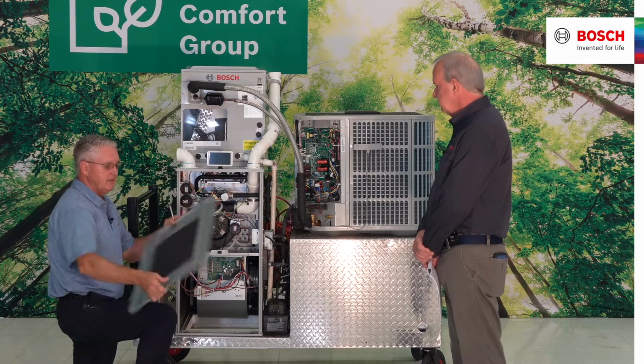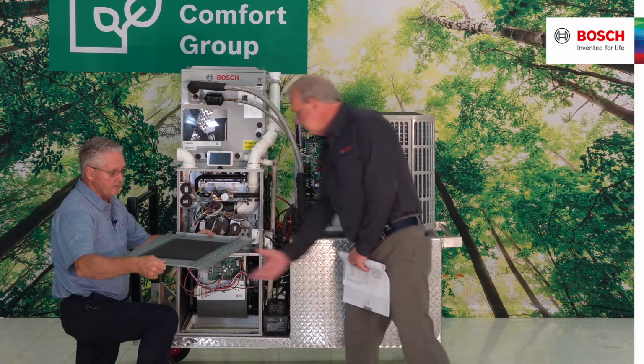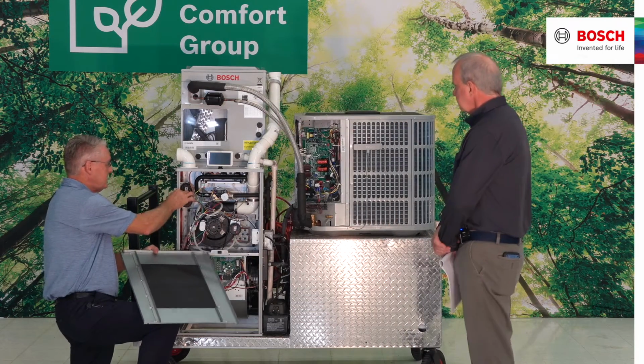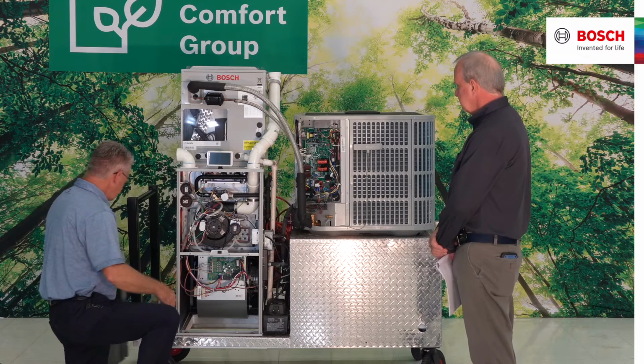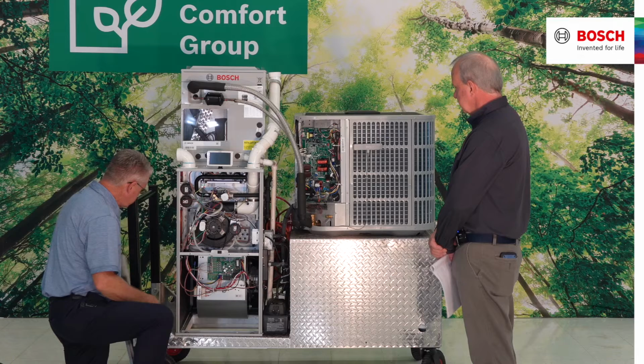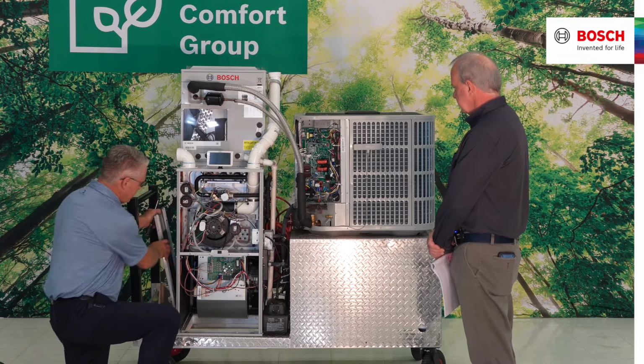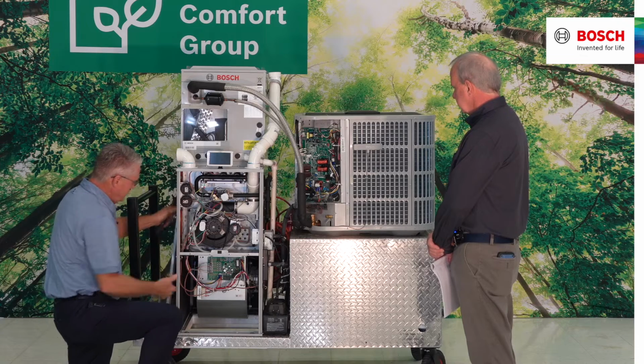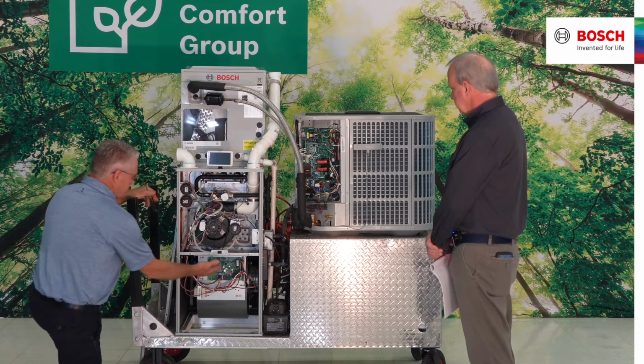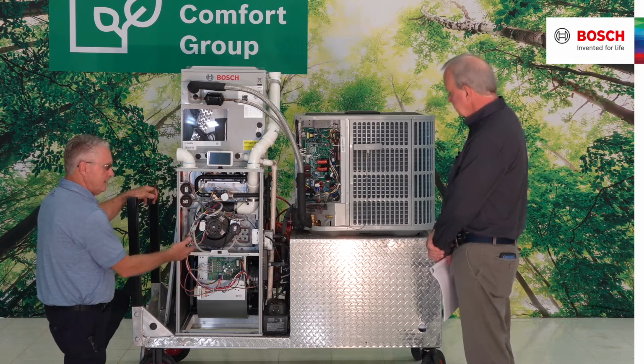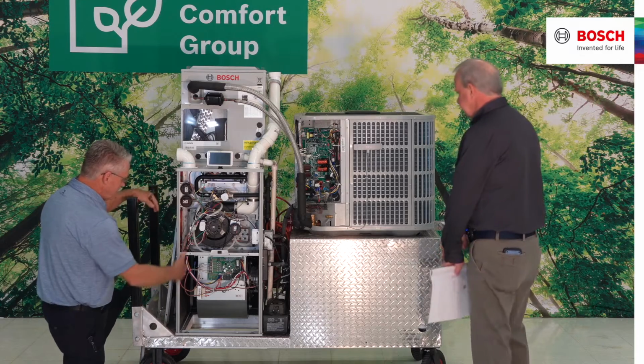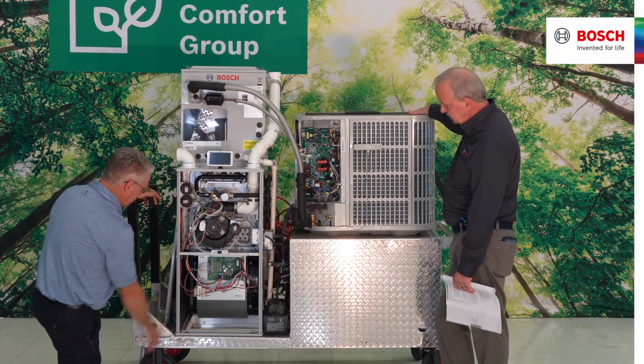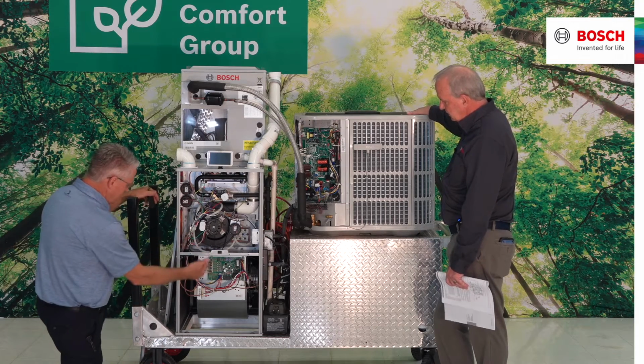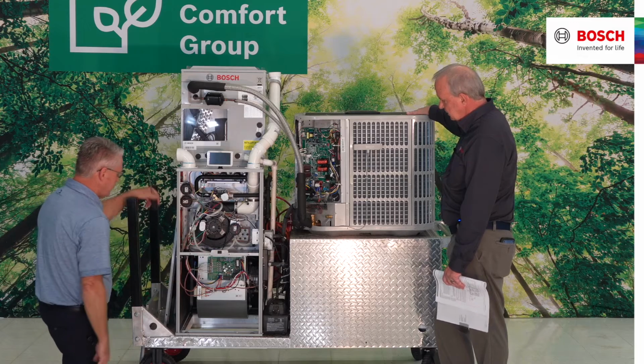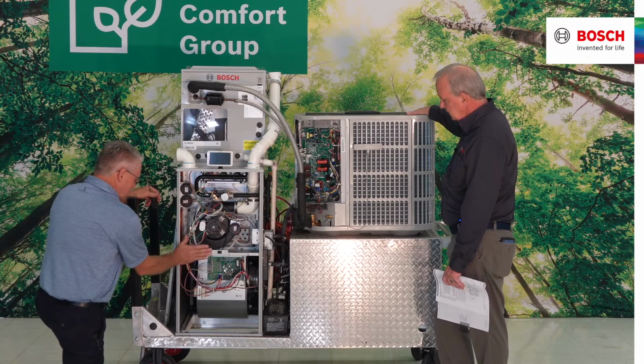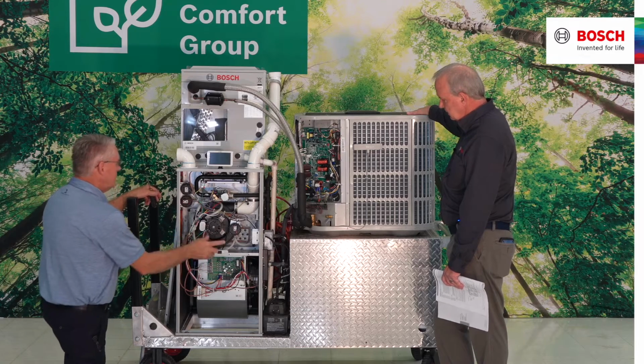It's ready to go. This is a very, very heavy piece of metal. It is a very, very heavy outside skin cabinetry furnace. But today, now I've got this bottom panel off. This is where all of my controls are. This is where my thermostat wires come into play, where I can hook it up to the board. It also allows me full direction of my fan control, my board, and all the electronics. This is where my transformer is located. In my fan motor, I can take out two screws and slide it out if I need to, put it back type situation. But again, the bottom panel must be on this unit when it is in the heat mode.